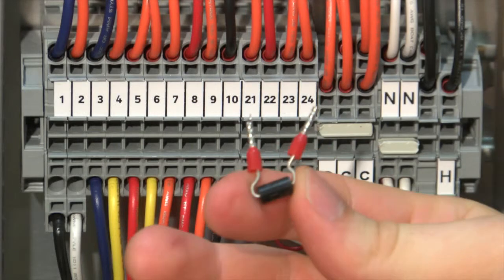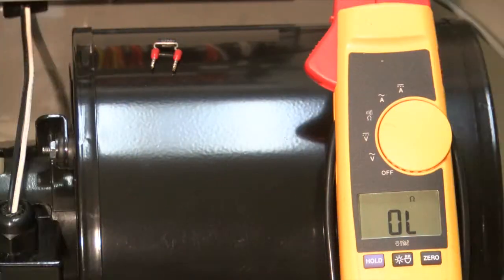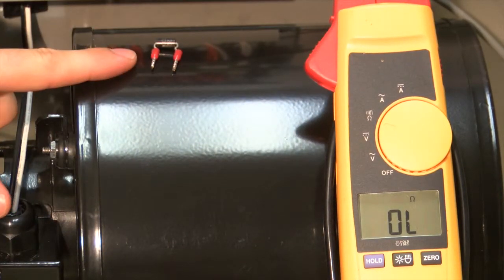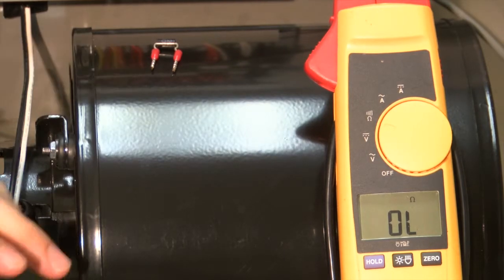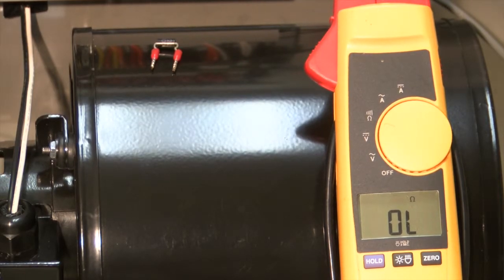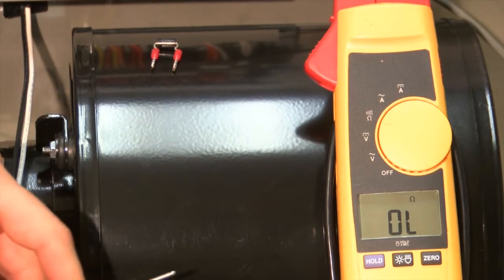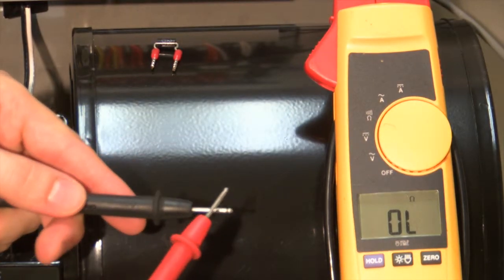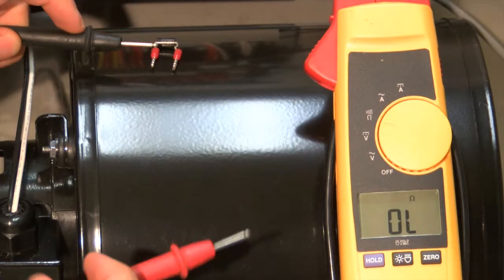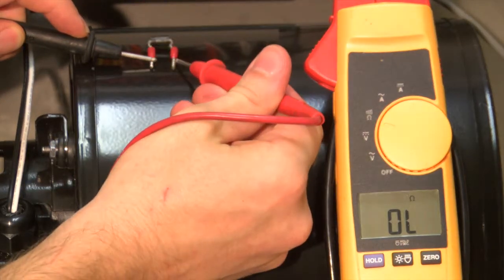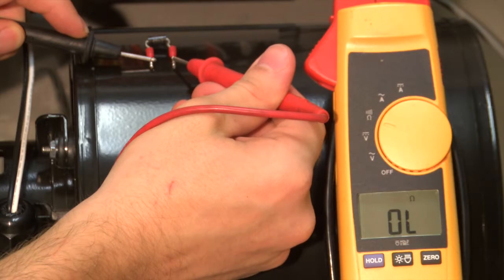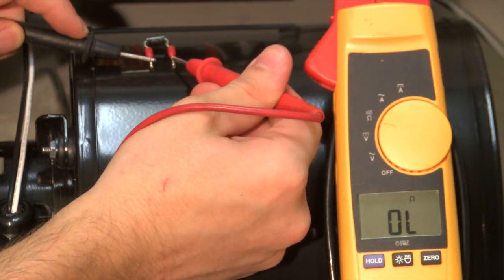Once you have the surge arrestor removed, we can check it. To check a surge arrestor, you want to check for continuity across it. A good surge arrestor will not have continuity across it. When a surge arrestor is blown, it creates a short or continuity across it to blow the corresponding fuse. If you take your voltmeter or multimeter and set it on continuity, you can place one prong on each side of the surge arrestor. A good surge arrestor will not have continuity across it.